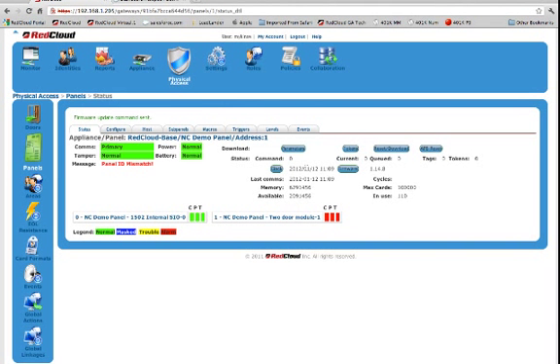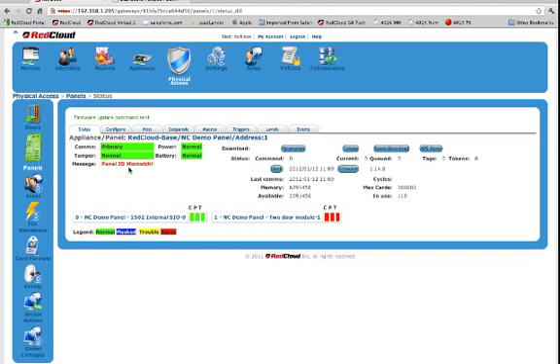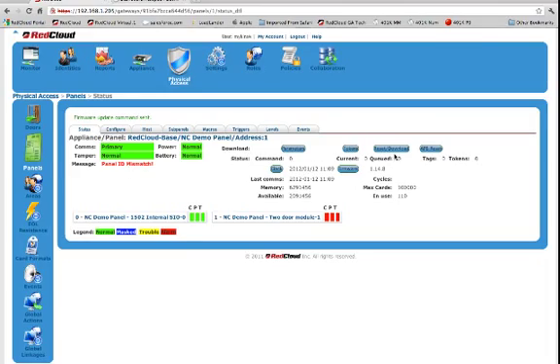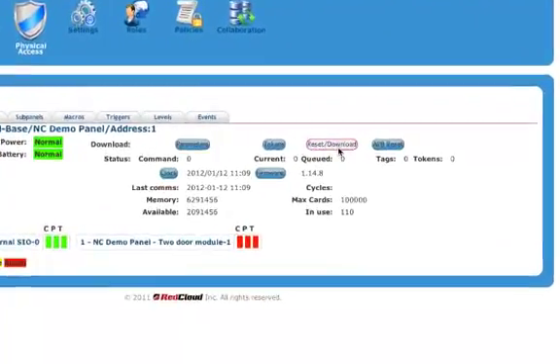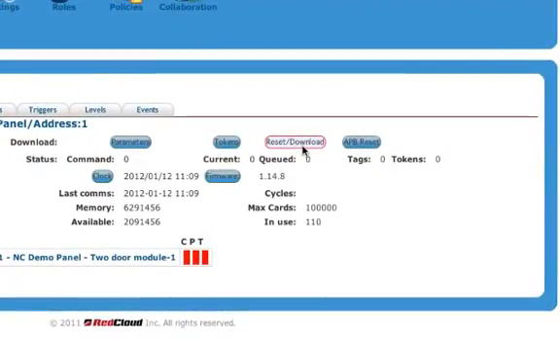Okay, so now my panel is finished downloading the firmware to the panel and that typically takes anywhere from one to three minutes for that to happen. But, you can still see that I do have a panel ID mismatch and the reason for that is because this panel in particular was connected to another system previously and it still has its last known database in it. So, now my next step is going to be to go in and hit the reset download.